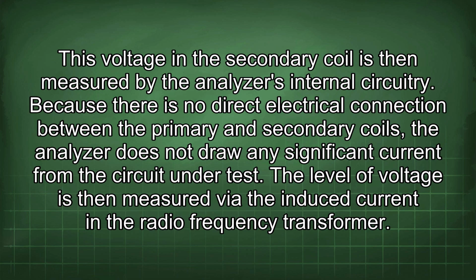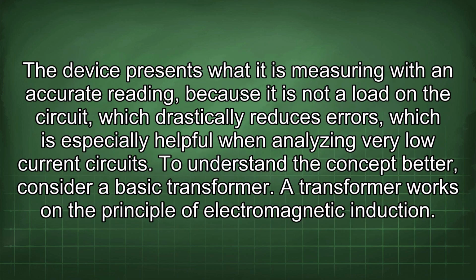The level of voltage is then measured via the induced current in the radio frequency transformer. The device presents what it is measuring with an accurate reading, because it is not a load on the circuit, which drastically reduces errors, which is especially helpful when analyzing very low current circuits.